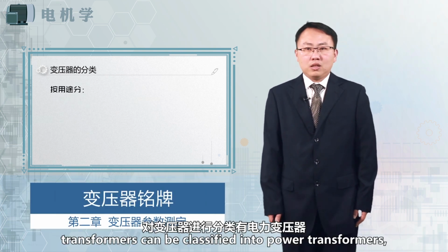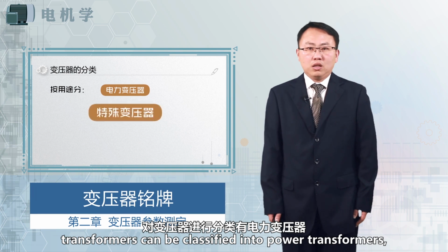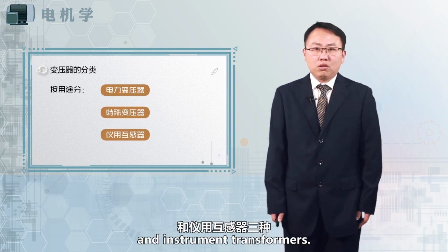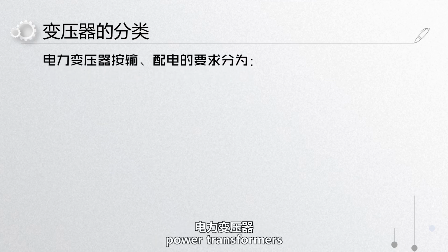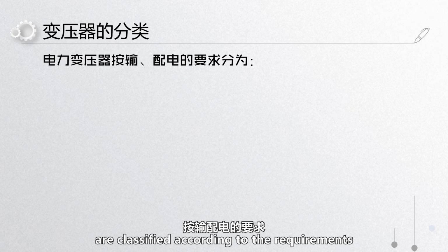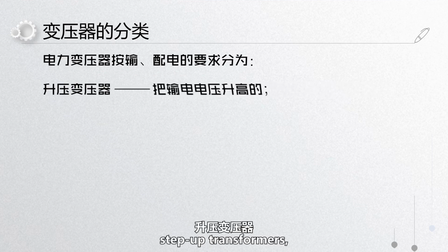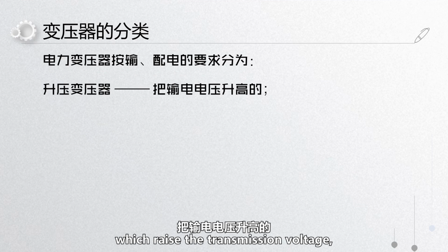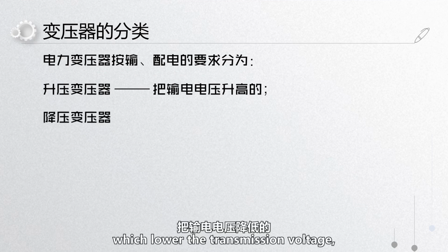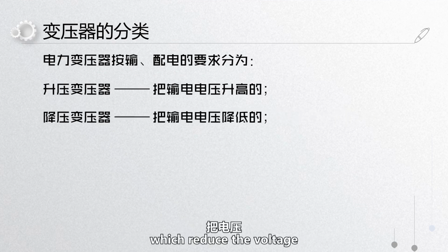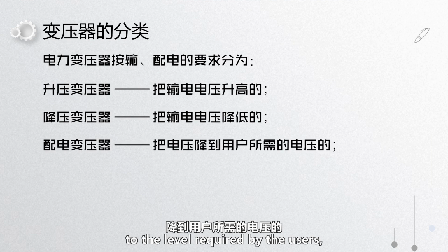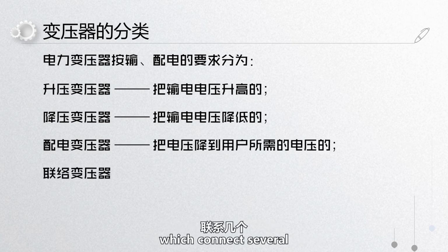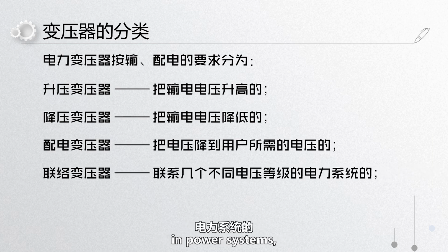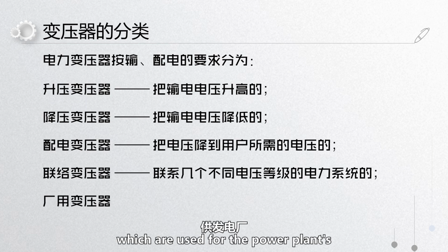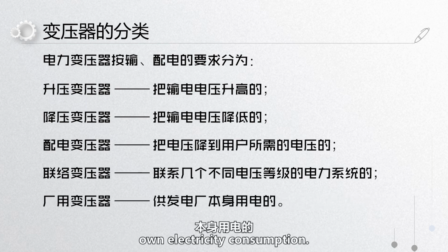According to their uses, transformers can be classified into power transformers, special transformers, and instrument transformers. Among them, power transformers are classified according to the requirements of transmission and distribution into step-up transformers, which raise the transmission voltage, step-down transformers, which lower the transmission voltage, distribution transformers, which reduce the voltage to the level required by the users, tie transformers, which connect several different voltage levels in power systems, and plant transformers, which are used for the power plant's own electricity consumption.